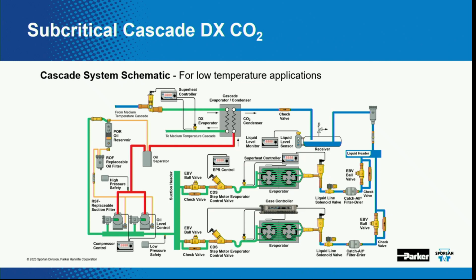I'm just asking why not use a fan? I've seen this on retrofits where they have DX racks on the roof and want to lower the charge, so they add a CO2 loop for low temp with just a brazed plate heat exchanger in between, and maybe another 5 or 10 years later they might get rid of the HFC rack. Yes, the HFC rack is basically what this is. You need essentially the chiller to chill this brazed plate heat exchanger. The reason we can't use a normal condenser, I'm going to get into in the transcritical mode, but basically you're not dropping your discharge pressure low enough.